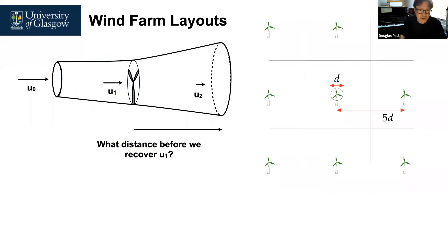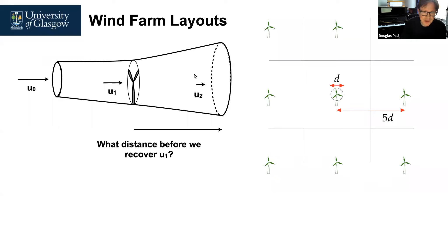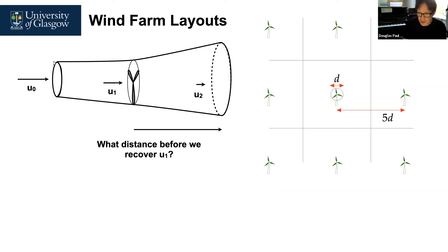There's always a question over how densely you can space wind turbines. Going back to streamlines and Bernoulli's equation, it comes down to how pressure changes and when it recovers back to the freestream velocity U₀. The rule of thumb used in industry and wind farm design is that you want turbines to be spaced by about five times the blade diameter. At that spacing, you get out of the wind shadow from one turbine and the next turbine on average is back to having U₀.